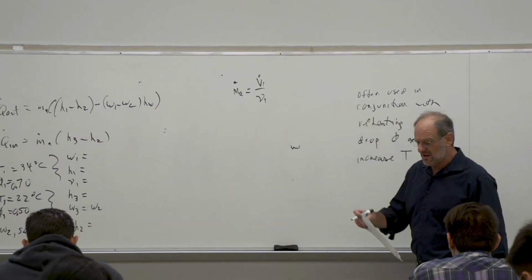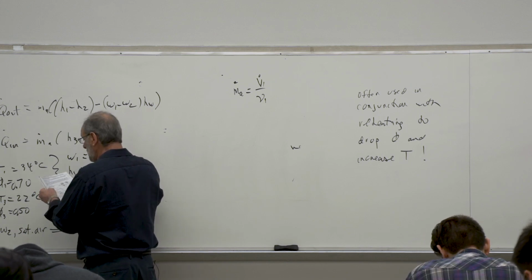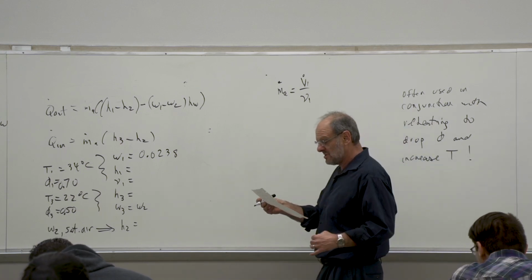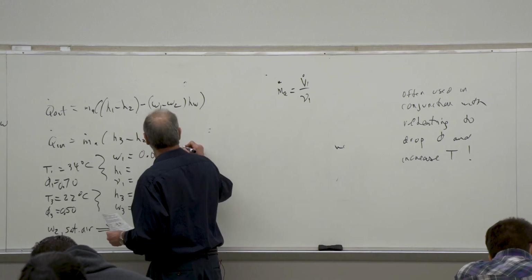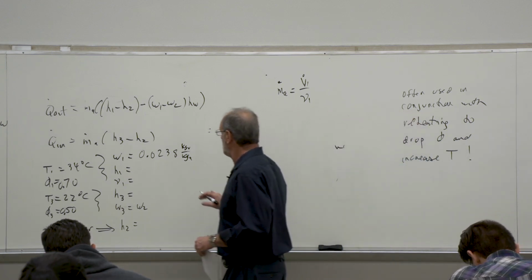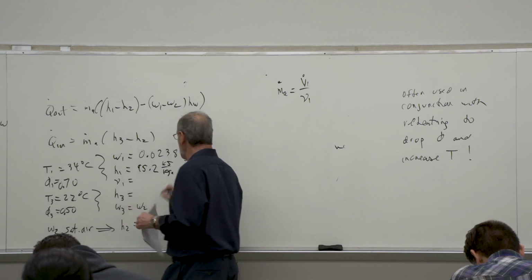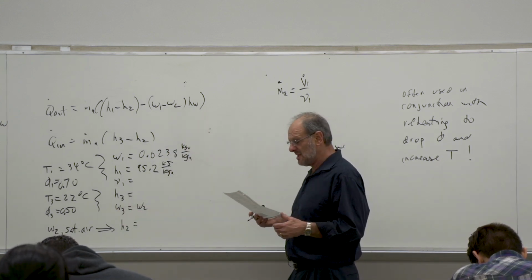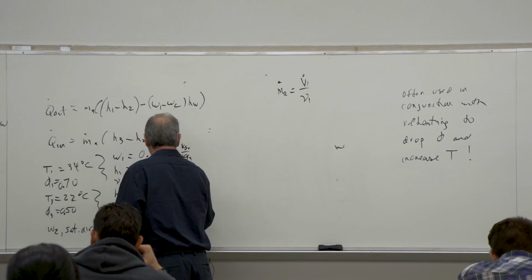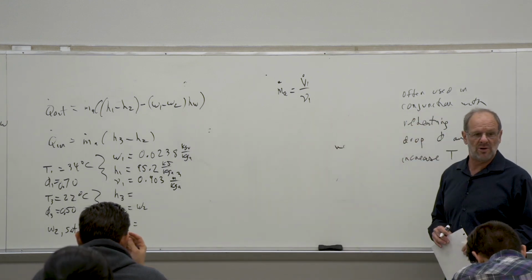All right, so now we can go into the psychrometric chart and pull out the data that we require. The humidity ratio, or specific humidity, if you will, is 0.0238. And if you have a chart, you can certainly follow along and see if you're getting numbers similar to this. So this is going to be kilograms of water vapor per kilogram of the dry air. Then we have our enthalpy term, so we get that to be 95.2 kilojoules per kilogram of the dry air. And then the specific volume we can also read. We are going to have to visually interpolate or estimate, but this becomes approximately 0.903 cubic meters, again, per kilogram of the dry air. So that's the data we need at point 1.